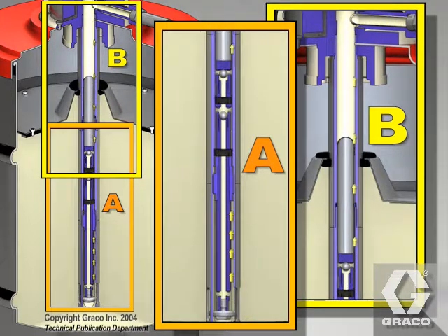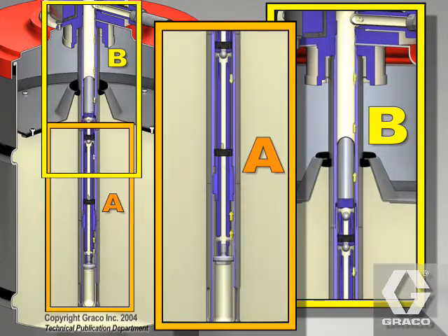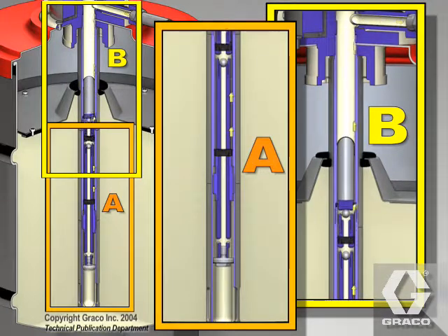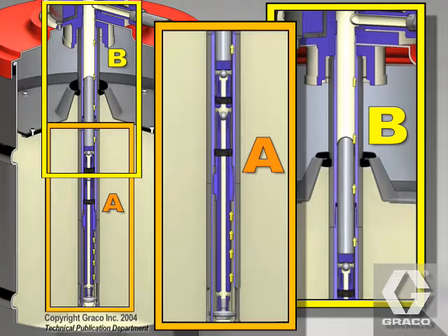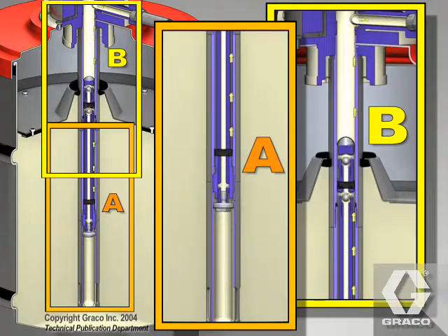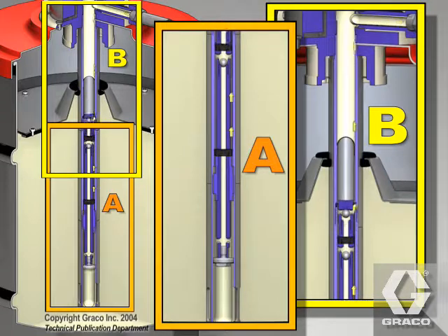On the next downstroke, the lower check closes and the upper check opens. As the pump piston moves down, the grease transfers past the upper check. Since the piston is half the size of the cylinder, half of the grease is pumped on this downstroke.